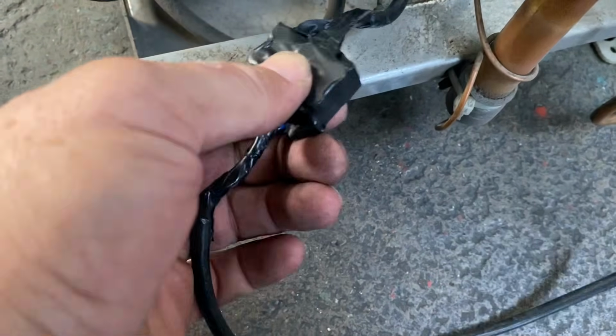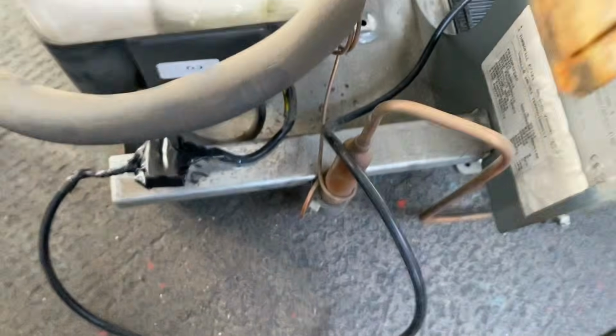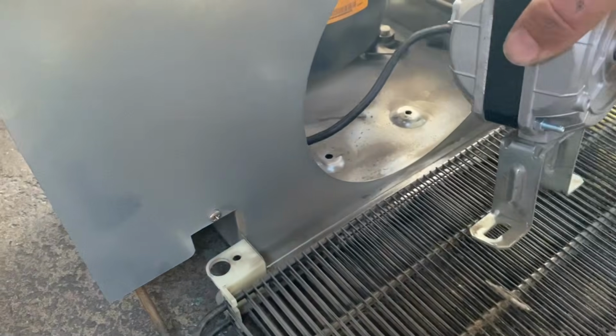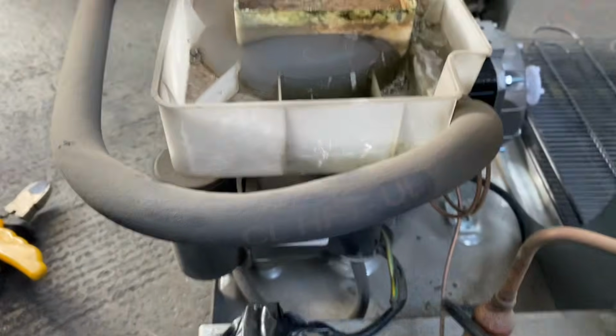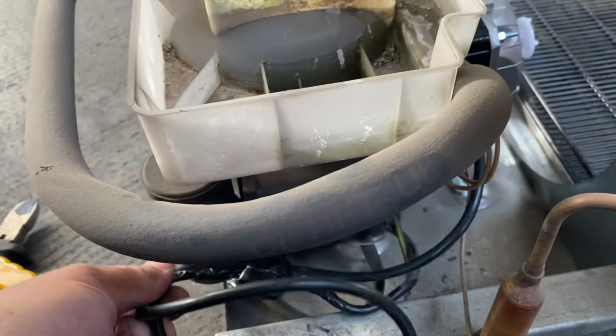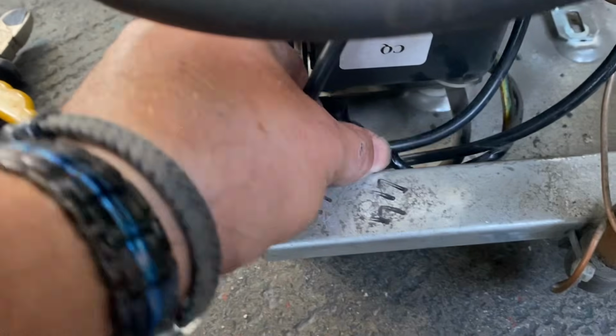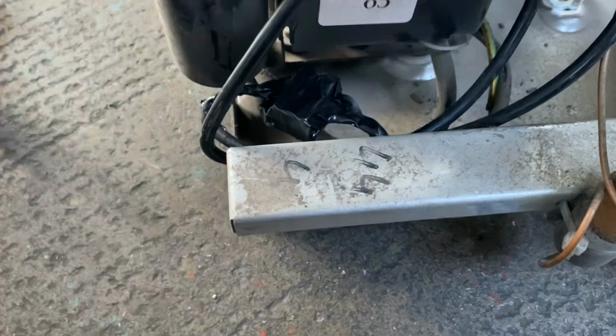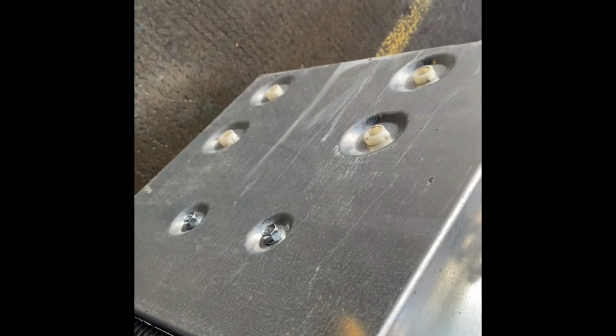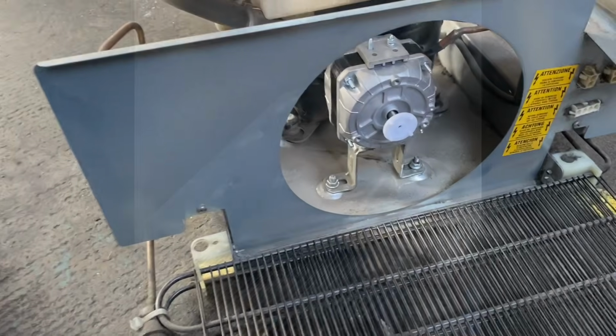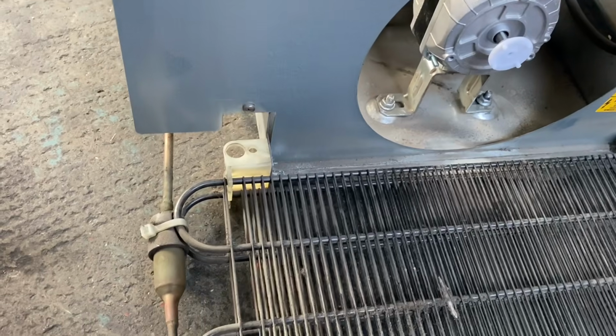Once you've done that, just make it all nice and tidy and clean by wrapping it up in some electrical tape so there's no risk of any contact with the base of the chiller. And then after that you need to reattach the fan motor to the base of the chiller, making sure that all the wiring is completely out of the way and it's not obstructing or getting in the way of the fan motor. You can see here we've put it back on and we've tightened the bolts back up so it now sits nice and flush with the base of the chiller unit.